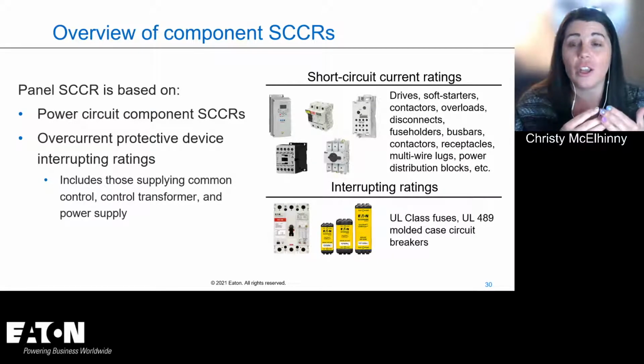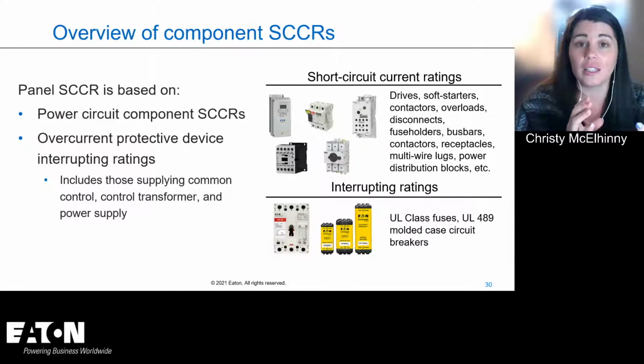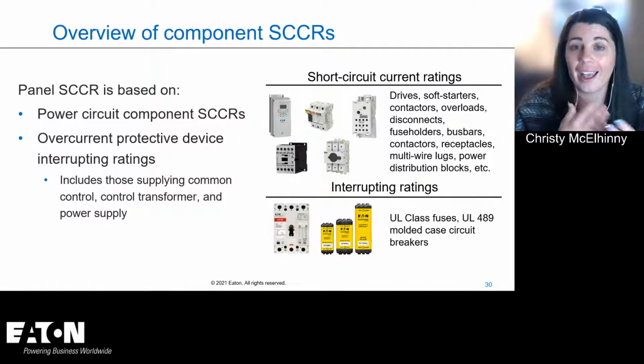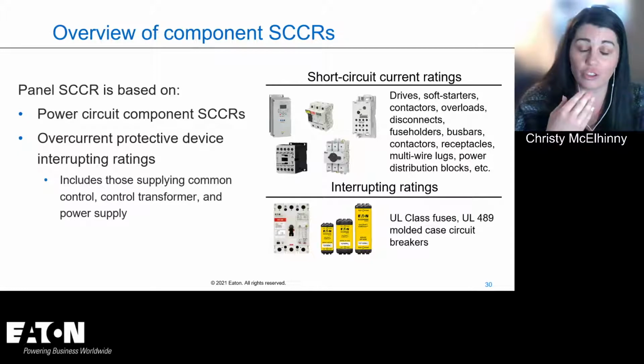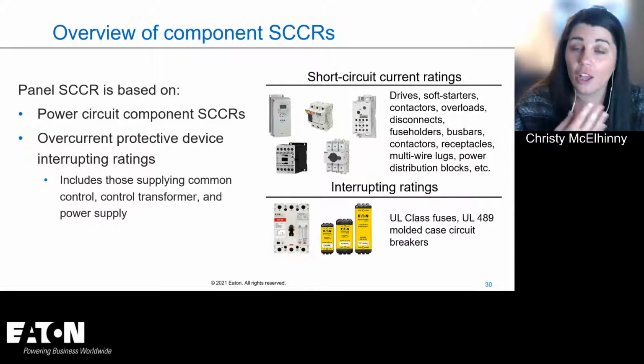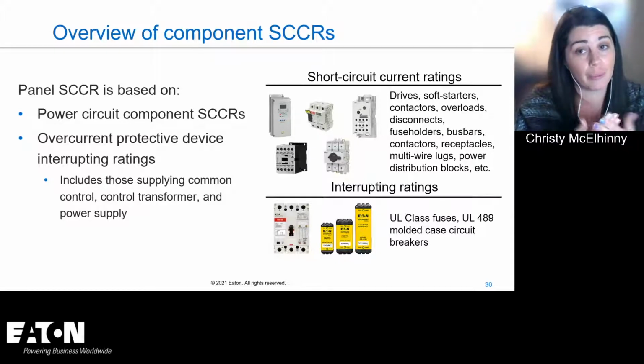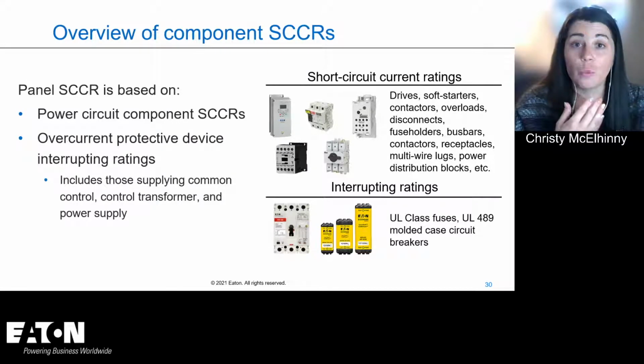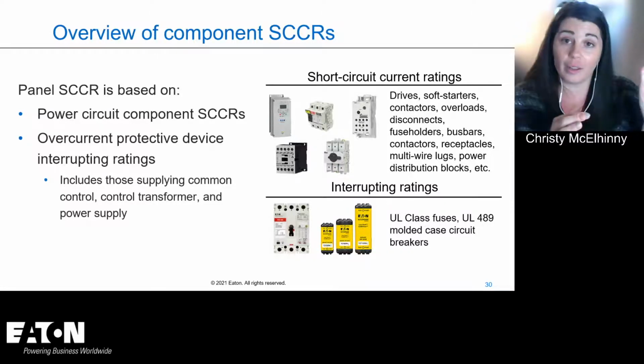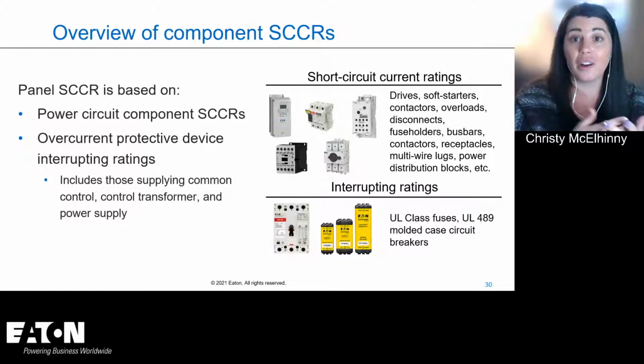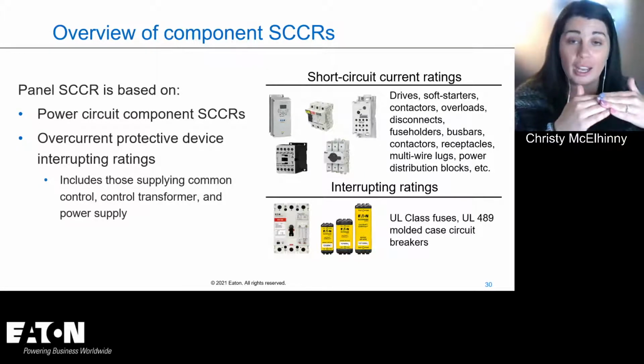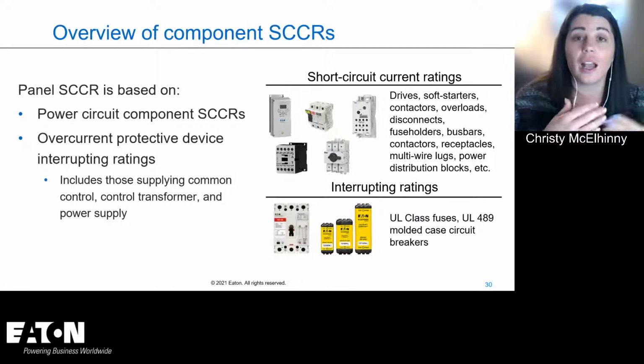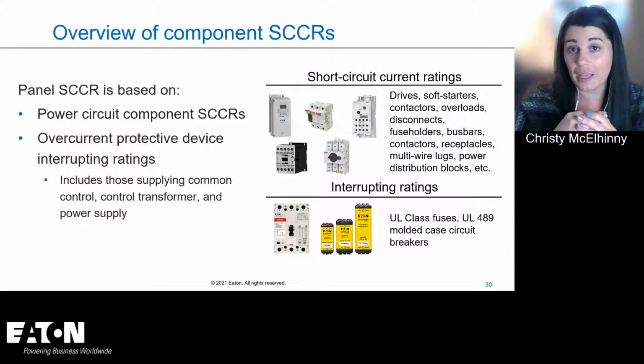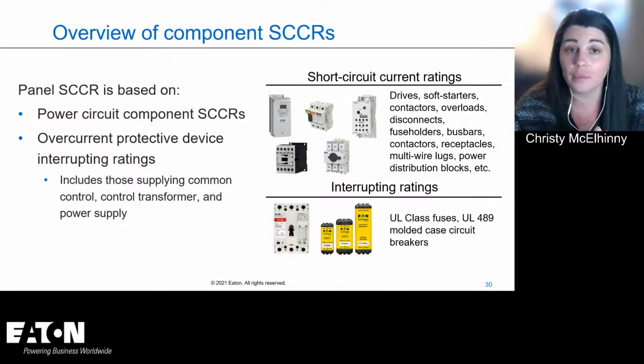Because short circuit current ratings, we mentioned, are similar to that withstand rating. The idea is these are the devices inside your panel that are not active during a short, right? They are sitting there. They are trying to withstand the amount of energy they are seeing while they wait for an upstream overcurrent protective device to open and protect them, right? And these devices, that short circuit current rating can change depending on what's in front of it. So if you have a current limiting fuse versus a non-current limiting breaker or no overcurrent protective device at all, please don't do that. But it can withstand a different amount of energy depending on what that upstream device is, how fast it opens, whether it's current limiting. That's your short circuit current ratings can change because they are dependent on another device for what they are.